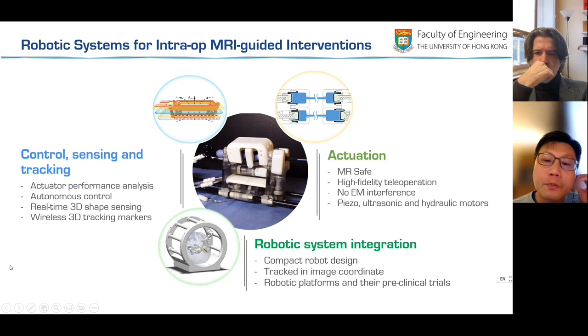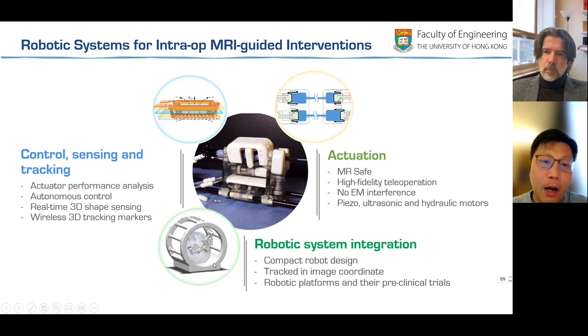Another thing is that the donut is very small. The MRI circle is actually very small. We even have to make a robot smaller than some coils. For example, for neurosurgery, we need an extra head coil to cover the patient. Therefore, we have to make the robot even smaller than the head coil, so that the head coil can accommodate the entire robot system.